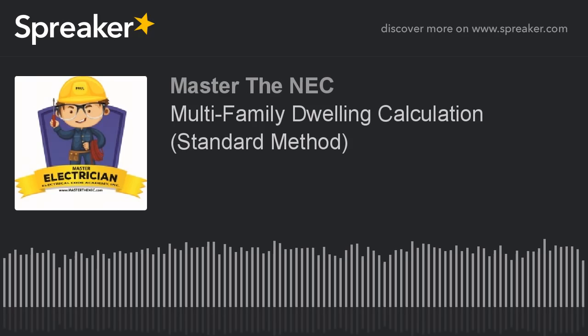So at this point, I have 54,000 for the 2 small appliances times 18 units, and then the laundry circuit, 1,500 times 18 equals 27,000. So 54,000, 54,000, and 27,000 equals 135,000 VA. Okay, so that was step 1.